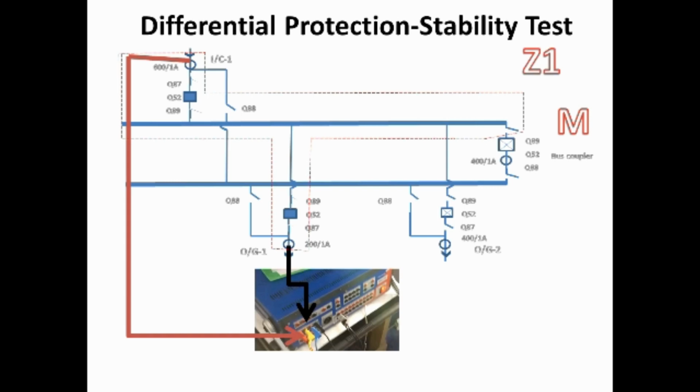If it is a green plant, then you can close the breaker and isolator live, but if it is already energized, then you can make a loop to give the relay feedback so that the relay may understand it is closed. Without giving this feedback you cannot test zone 1 and zone 2. The differential will not operate. So before going to the secondary injection, you have to close this contact.